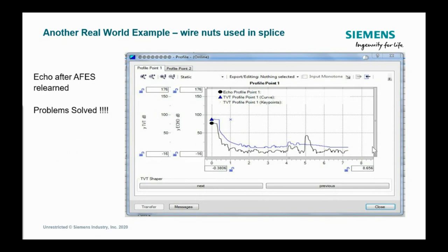So what I did suggest to them is take out the yellow wire nuts, solder those connections together, and from there we can get a good, clean electrical connection. If you use wire nuts, it's not if it's going to fail, it's when it's going to fail. And typically in wastewater, you're going to get six months, maybe a year out of it, till you get enough resistance in that wire nut connection before you start to have problems. So that's one of those.